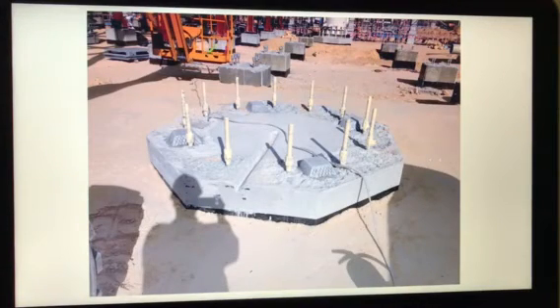This is the foundation after chipping — you can see some material has been removed from the surface. The bolt is protected with masking tape to avoid rusting, though it is not a fully reliable method. You can also see a slope line on the surface. When curing is done, QC will ask you to do a slope test, a post-pour survey report, and also a compression test.